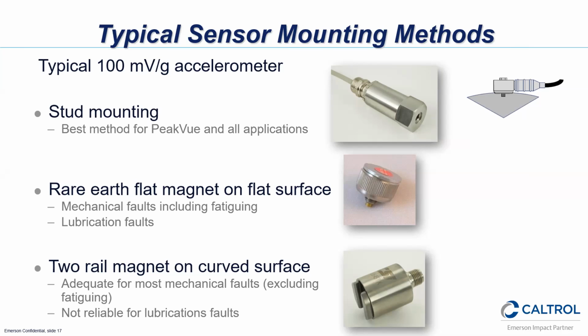But once they're installed, they're generic. They're 100 millivolt per G. It's a very common accelerometer in the industry. They run out to a BNC connection, and they'll run with any other manufacturer's analyzers, so they're not tailored to one type of analyzer manufacturer. Once they're on there, they stay for the life of the machine. You just take them off when you change bearings and whatnot, and retap them and put them back on.